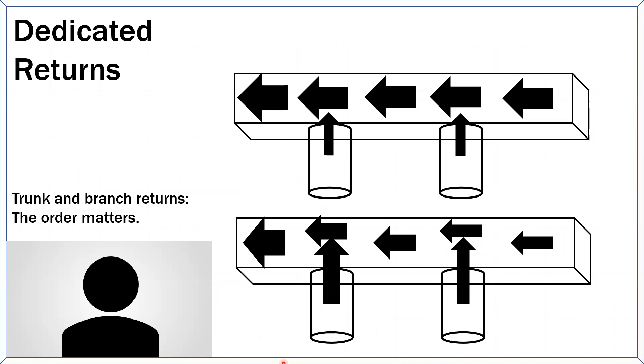And it just so happens that the bedrooms are always the far ones away, the ones with the little returns, and they come in at the end, while the big one is always near the unit, disrupting the flow of air big time. So you get these giant pressure losses and resistances on these trunk and branch systems.